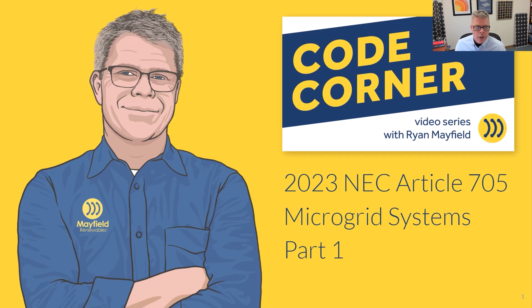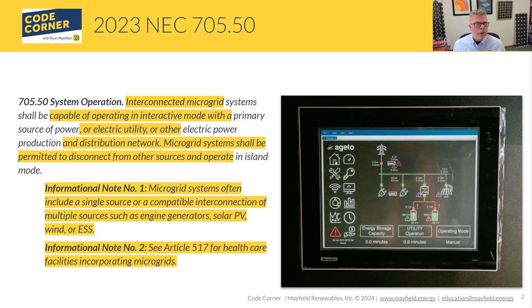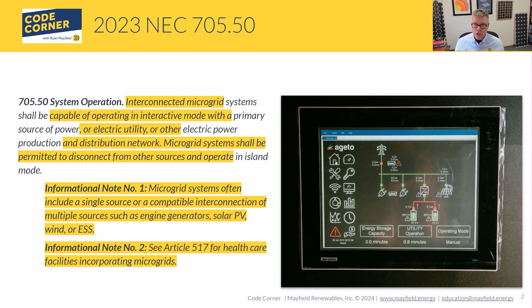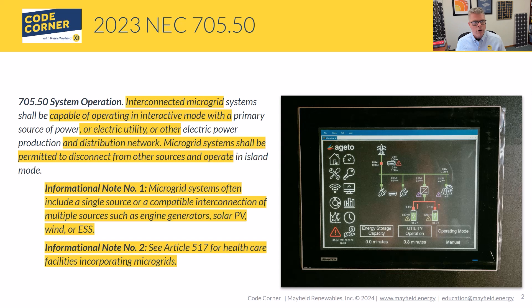One of the things that's probably super helpful when talking about microgrids is to define what a microgrid is. You'll find a definition in Article 100, which talks about a microgrid being an electric power system capable of operating in island mode and capable of being interconnected to an electric power production and distribution network. In short, in the eyes of the NEC, we have power production sources and a primary source of power.